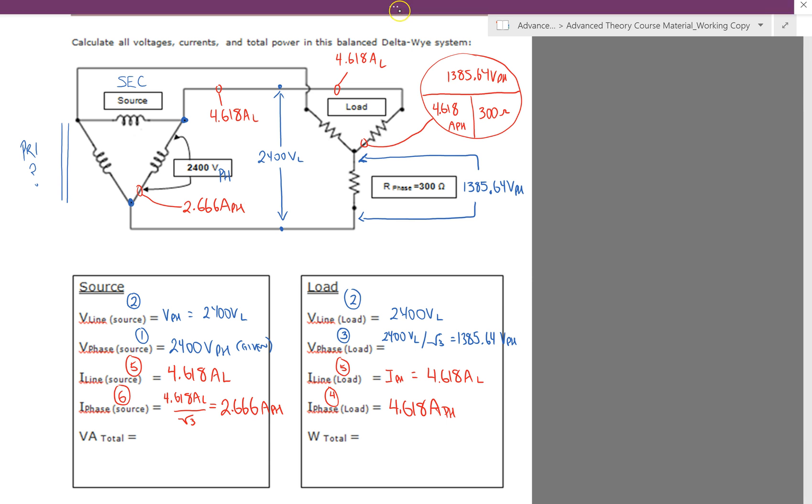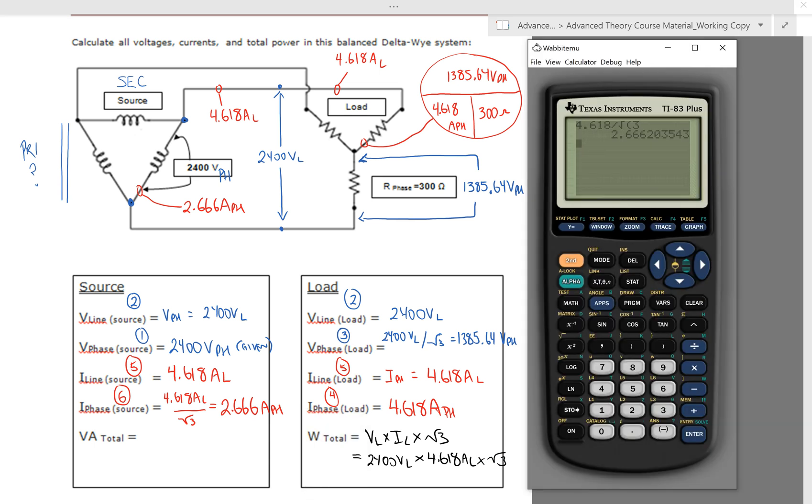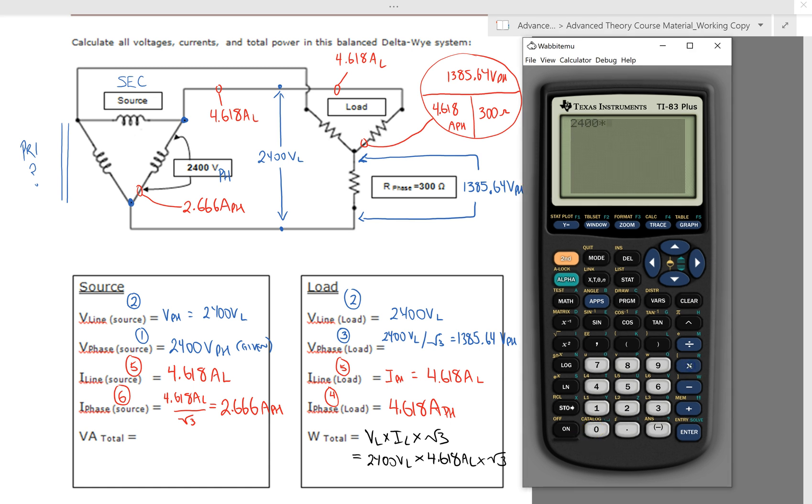And then the last thing we need is the total wattage. So we'll do V line times I line times root three. So in this case, the V line over here is 2400 volts on the line. We'll multiply it by our current 4.618. So make sure you grab the right values there. And we'll multiply that by root three. So let's see, we've got 2400 times 4.618 times the square root of three, and that gives us 19,196. Beautiful.